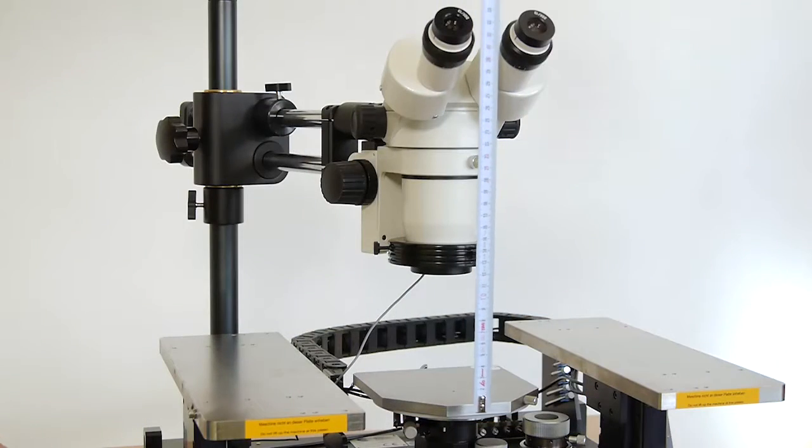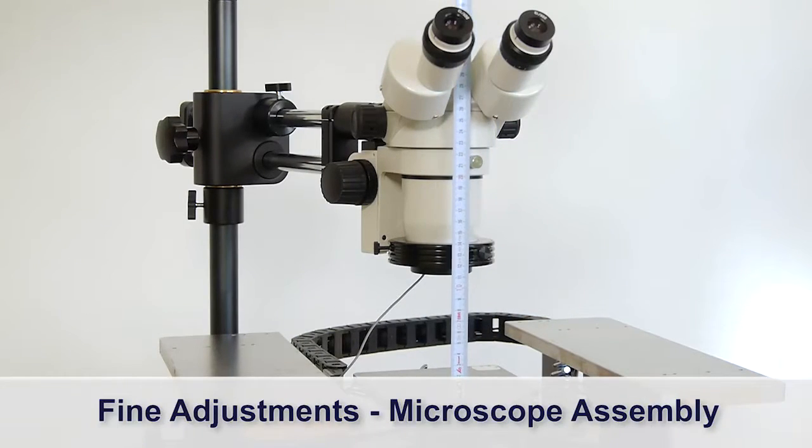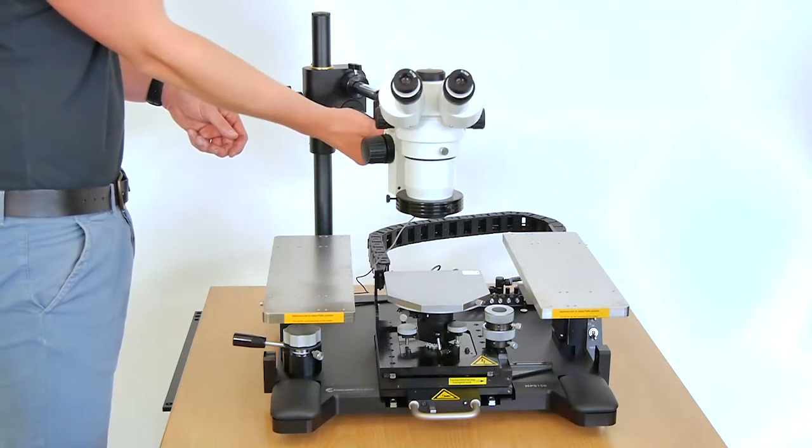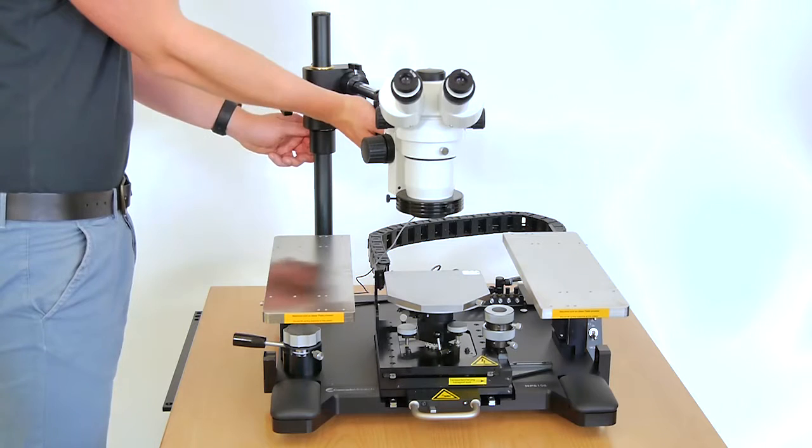If necessary, re-adjust the set height of the microscope. The recommended working distance is 113mm. For this, secure the crossarm at first with your hand and then unlock and adjust the clamping collar.